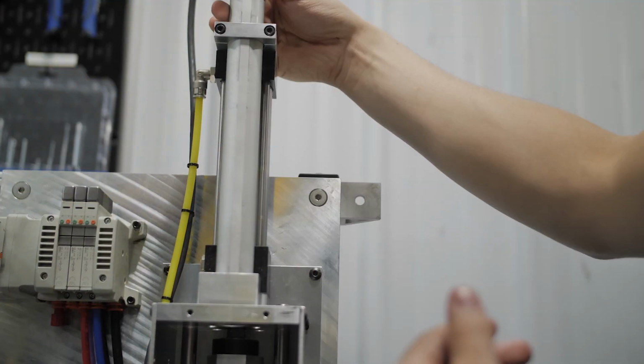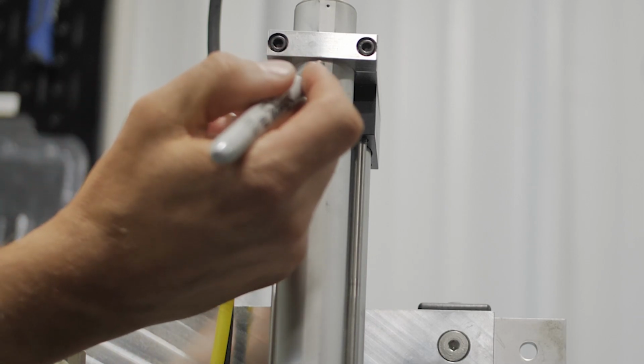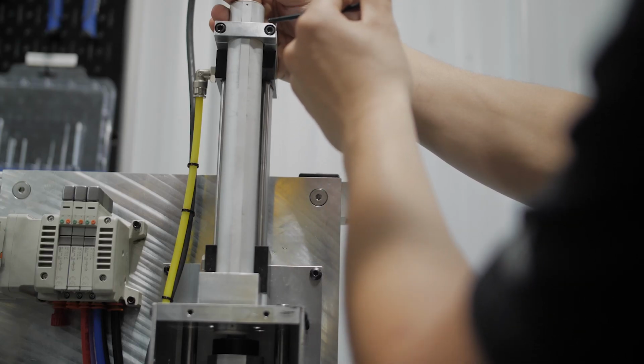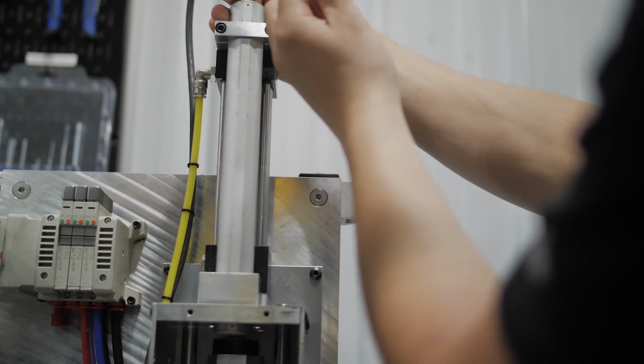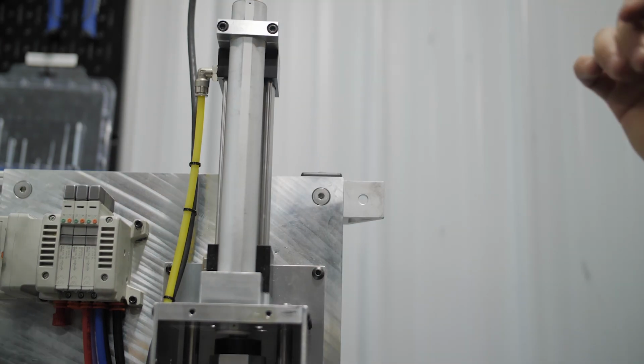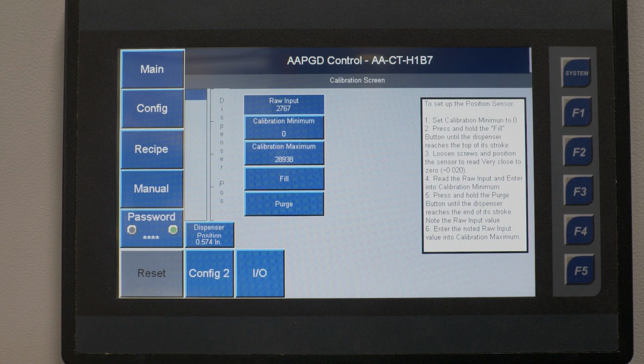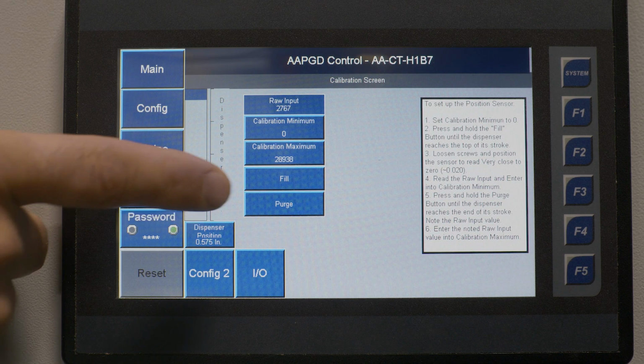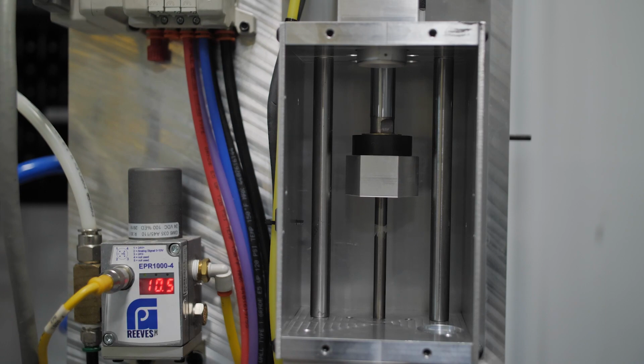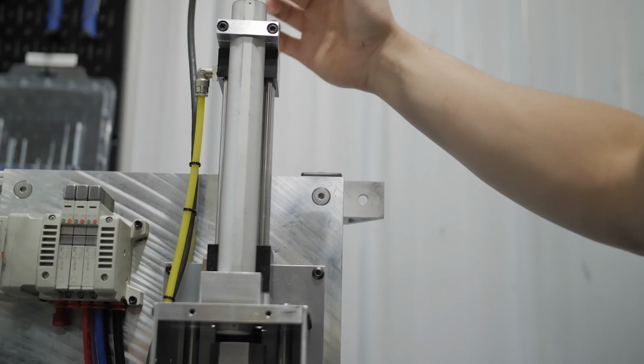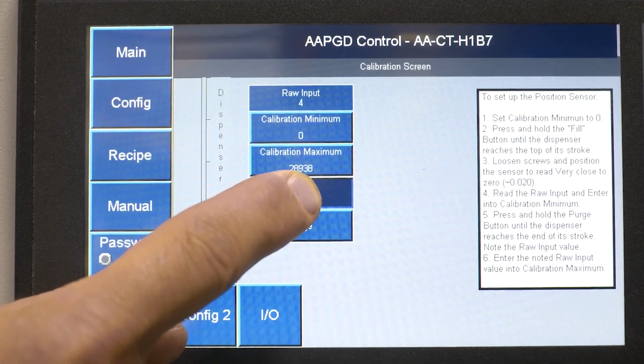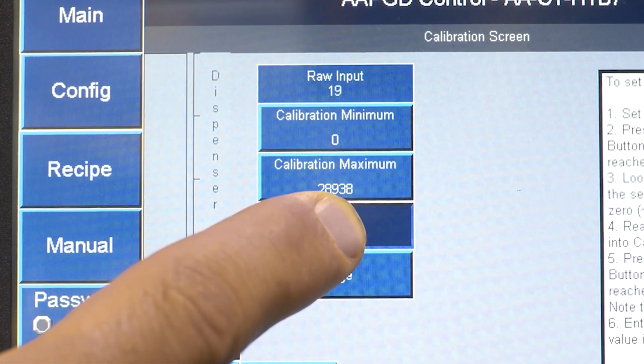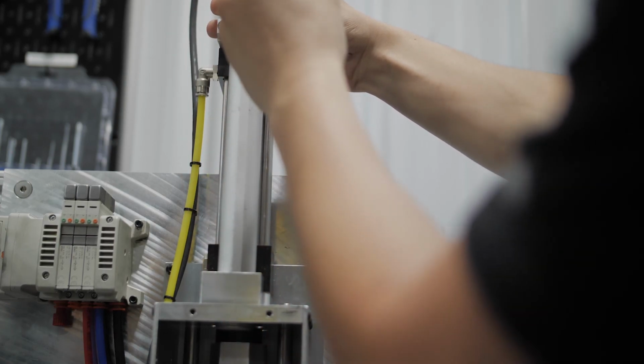If you need to replace or reset your linear position sensor, you can loosen these 2 screws right here. To recalibrate it, there may be a Sharpie mark at the top, and you can slide that to where you can just barely see it and tighten the 2 screws. If your sensor has no markings on it, you can go into the config screen and go into your calibration screen after that. There you will see a fill button. When you hold that, the cylinder will retract all the way, and you want to position your linear position sensor to when the raw input is around 0 to 50. That looks like a good spot.